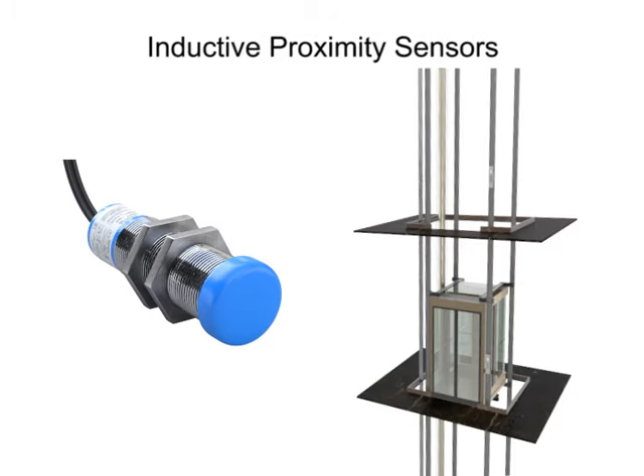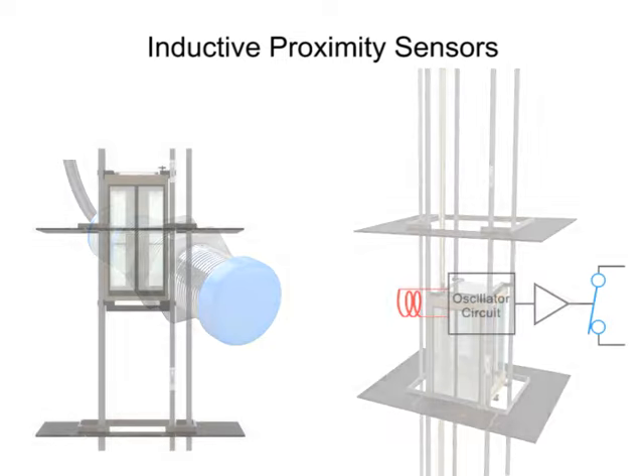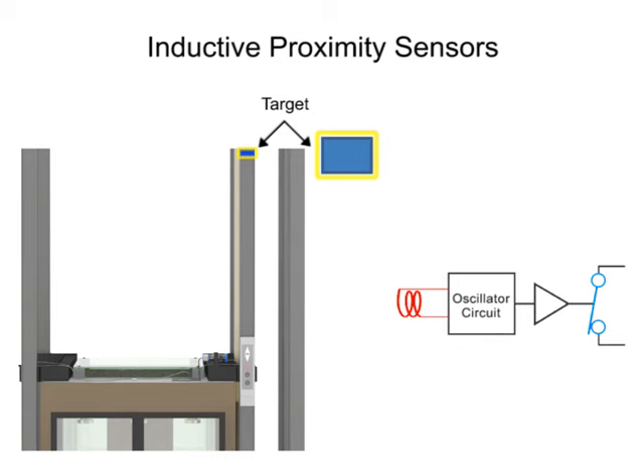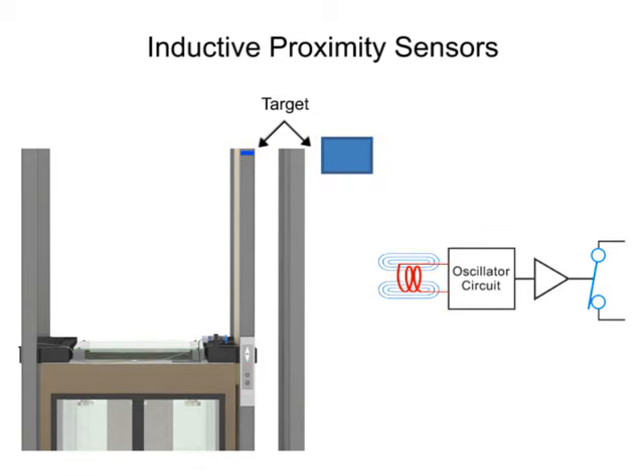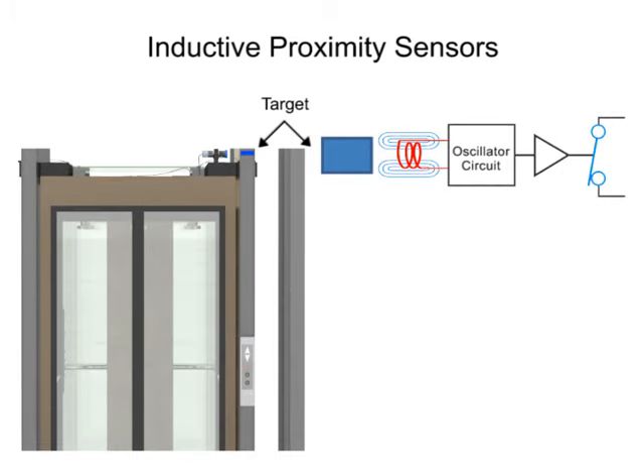Inductive sensors can detect a target from 0.5 mm to 40 mm. They only detect metallic targets and therefore use a magnetic field to detect its presence. When a ferrous metal material enters the magnetic field, electrical currents known as eddy currents are induced on the metal surface. These eddy currents induce a power loss within the oscillator circuit and in turn cause a reduction in the amplitude of the oscillations. This is known as the ECKO, or eddy current killed oscillator, principle.